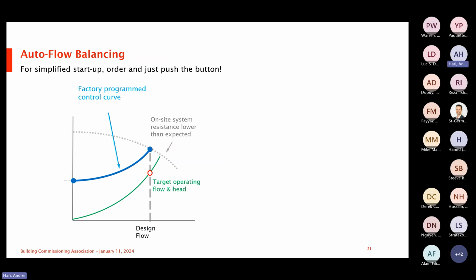Also, there's a function available called auto flow balancing. What we typically know in our industry is that engineers will always overestimate the head in their systems. It's easier to slow down a pump than to take a pump out and increase its size if there's an error in calculations. But when we have oversized pumps, typically the pump is going to operate to the right of the system curve. Auto flow balancing affords you the ability of just saying, this is my design flow, and it will balance the pump, that is, adjust the design point speed based on the resistance of the system. So it gets you right back to where you need to be, and then it locks in on that point. That's the other functionality available in this type of technology.